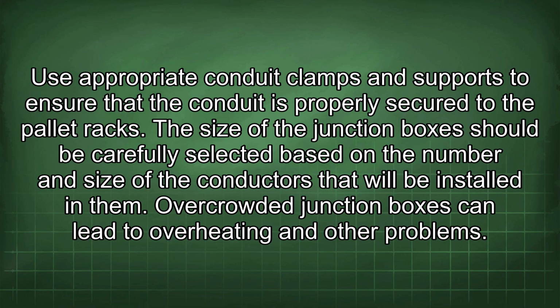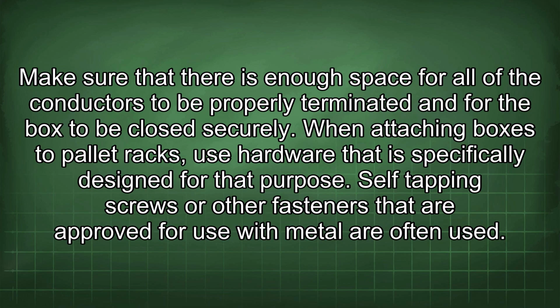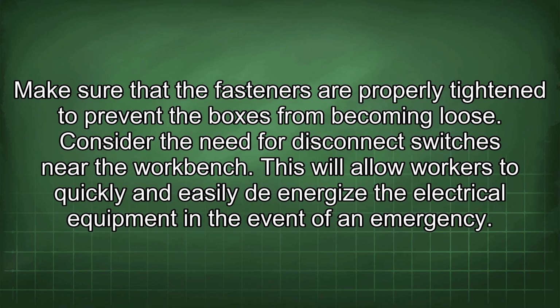The size of the junction boxes should be carefully selected based on the number and size of the conductors that will be installed in them. Overcrowded junction boxes can lead to overheating and other problems. Make sure that there is enough space for all of the conductors to be properly terminated and for the box to be closed securely. When attaching boxes to pallet racks, use hardware that is specifically designed for that purpose. Self-tapping screws or other fasteners that are approved for use with metal are often used. Make sure that the fasteners are properly tightened to prevent the boxes from becoming loose.